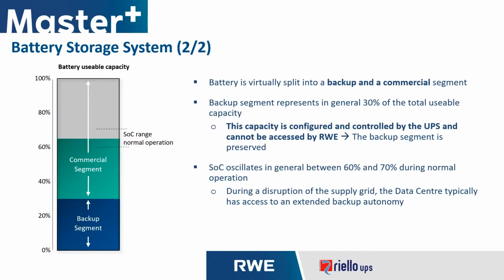The battery storage system is virtually split into a backup and commercial segment. The backup segment represents in general 30% of the total usable capacity. This capacity is configured and controlled by the UPS, and therefore it cannot be accessed by RWE at any time. The backup segment is preserved only for the IT load. During normal operation, the state of charge will oscillate somewhere between the 60 and 70% marker. The reason for this is that it depends on the frequency of the electrical system.